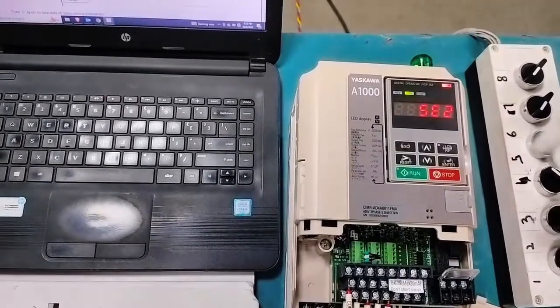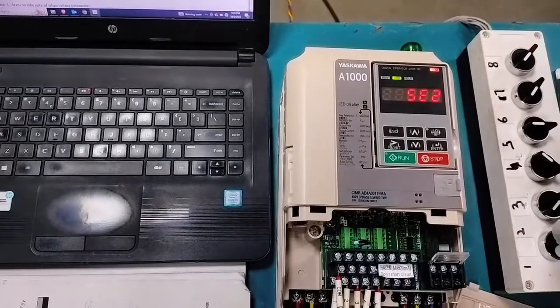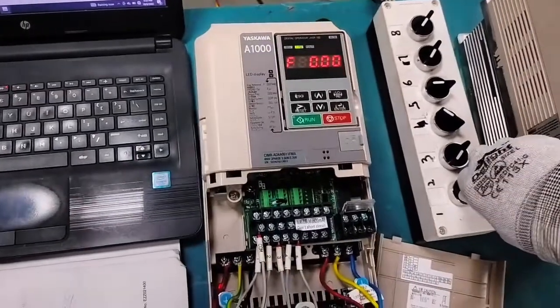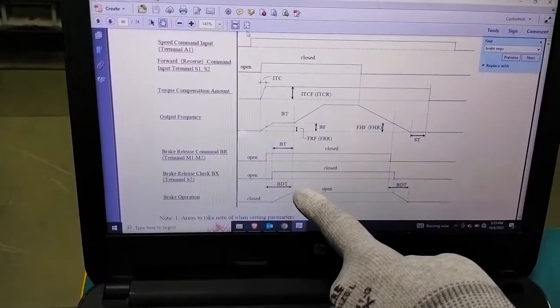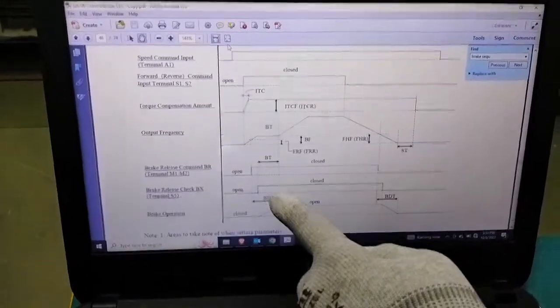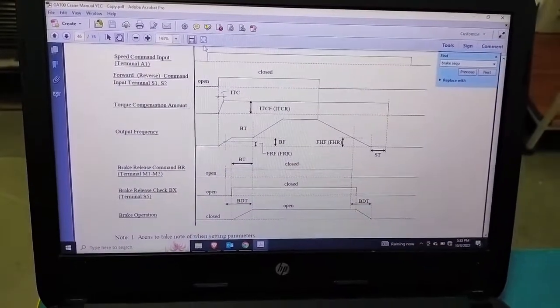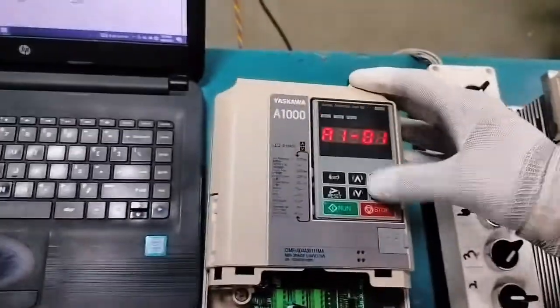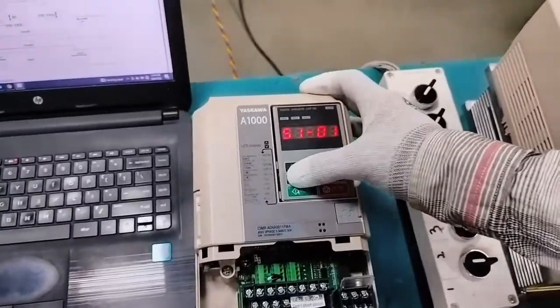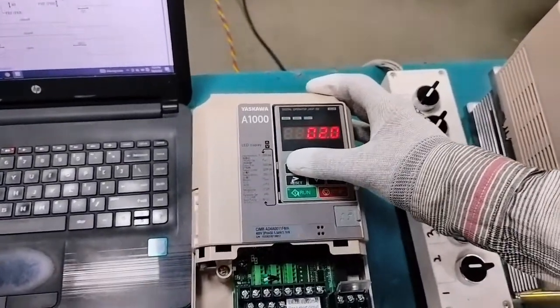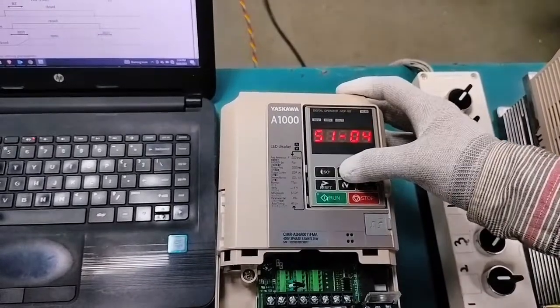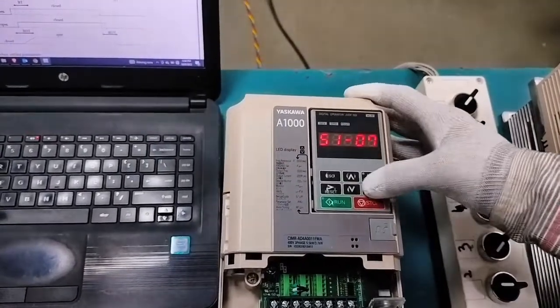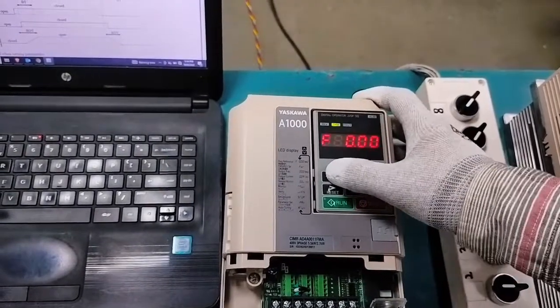When I give the run command, it will show an SC2 or SC1 alarm. These alarms will keep coming in Yaskawa crane software because, as shown in the graph, the brake will open and output will go above the brake threshold only when the torque requirements fed in the S1 parameter group are met. In S1 parameters we can define various thresholds — brake frequency, output frequency before opening the brake, current, and torque — all defined as a percentage in both forward and reverse directions.